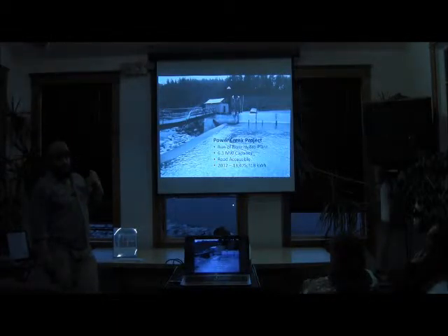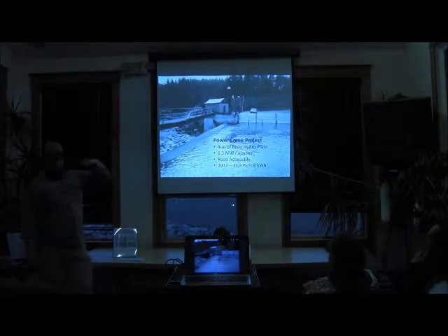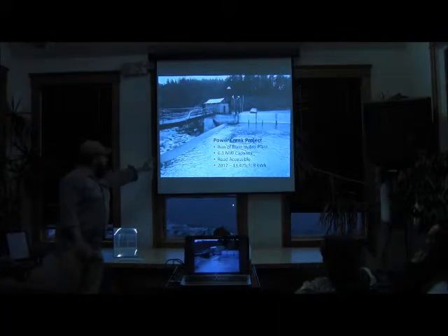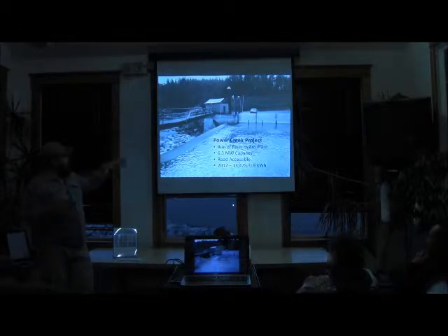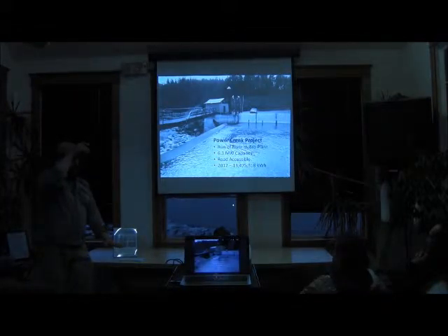So like a couple weeks ago when we had all that rain, we were spilling. In this reservoir, we keep a certain level. It stays at 7.5 feet. We don't want it to go over that, and we don't really want it to go below that. 7.5 feet is our optimal point. And this dam will raise and lower depending on the water level. When we had all that rain, a couple inches of rain on Saturday 2 weeks ago, above this dam there were 3 feet of water going over. It was 7 feet tall, and the dam was down at 4 feet.